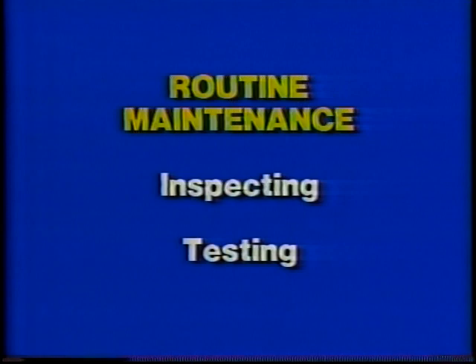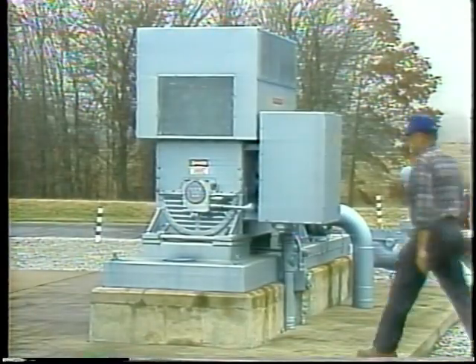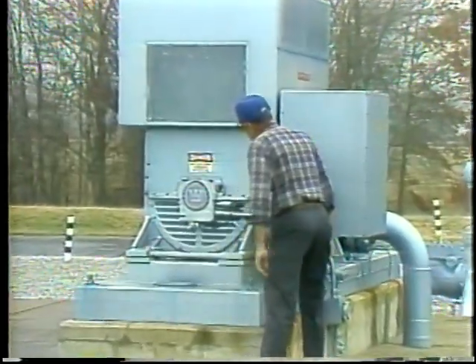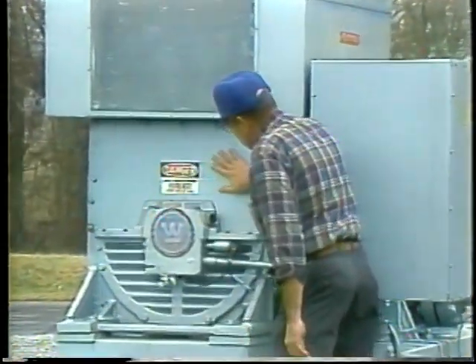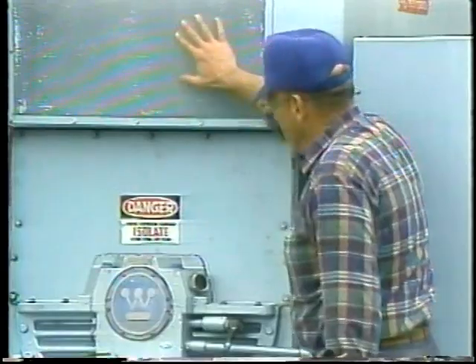Now, the other part of motor maintenance involves inspection and test on motors to detect problems before they become obvious or lead to a breakdown. Some of the tests are as simple as watching and listening to the motor. If a centrifugal switch flashes abnormally, something is wrong. The motor may still run all right, but the switch will probably fail soon. If an AC motor hums or buzzes, it may be under too heavy a load, or it might also have loose core laminations.